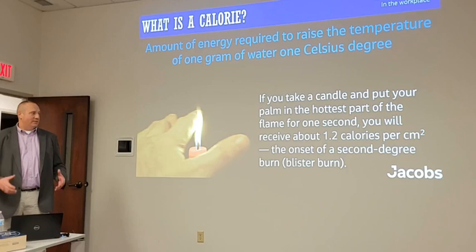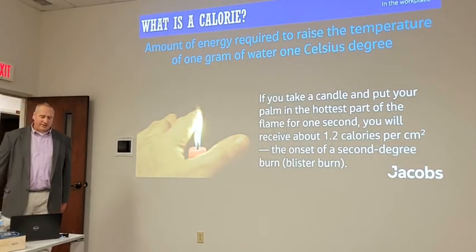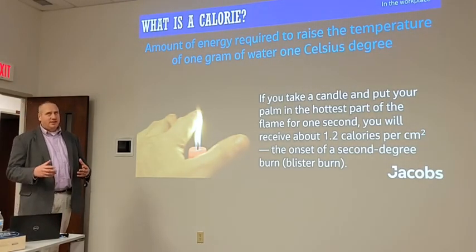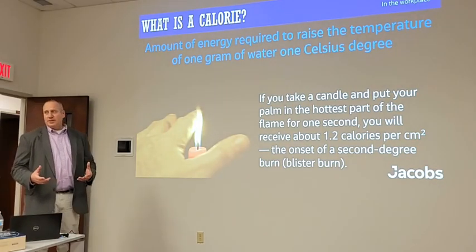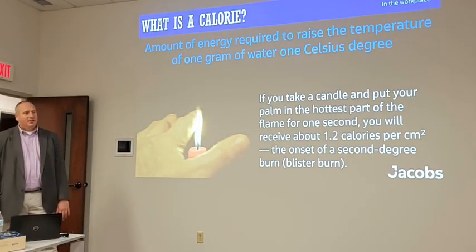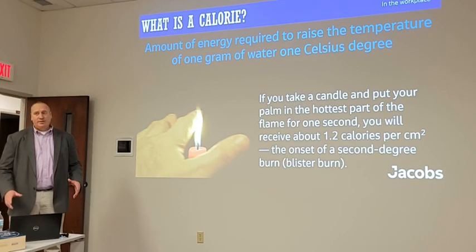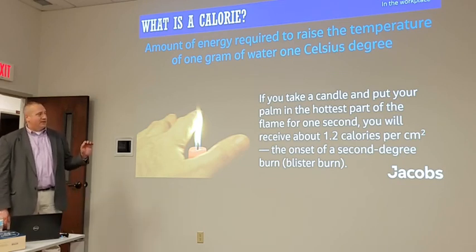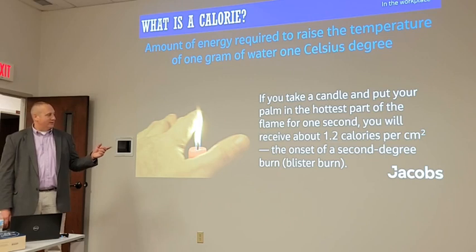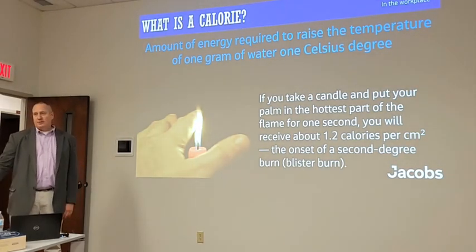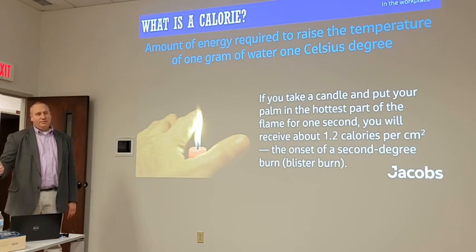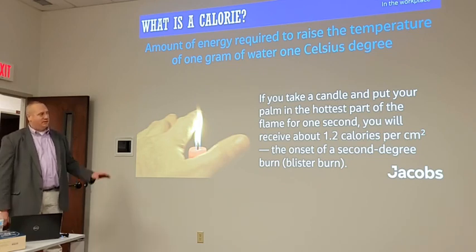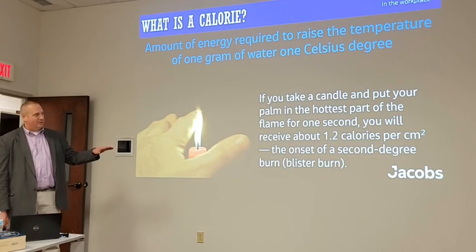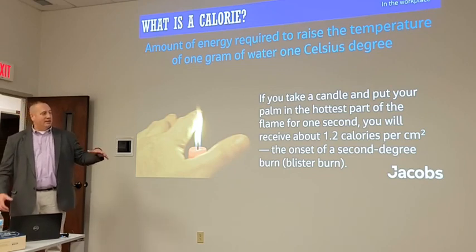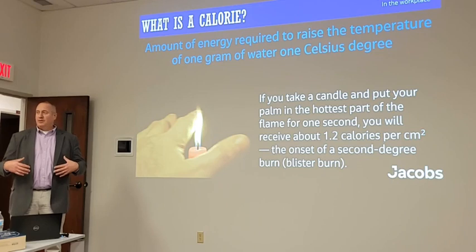And that's prior to the onset of a second degree burn. It's an exposure that doesn't require treatment, and that kind of falls in line with what OSHA determines as a hazard, something that requires some kind of treatment. However, you can imagine some of these synthetic materials, if you were to take a big lighter and hold it to somebody's clothing for a second, it could very well combust. And that's where, even though something's below 1.2 calories per centimeter squared, you can stand there with nothing on and it's not going to burn your skin.